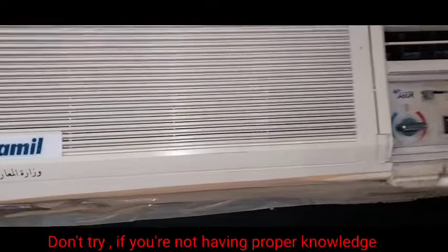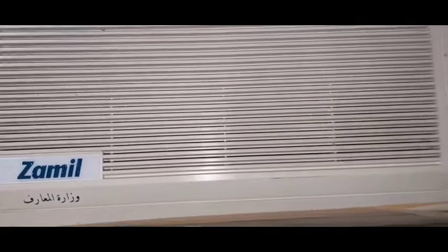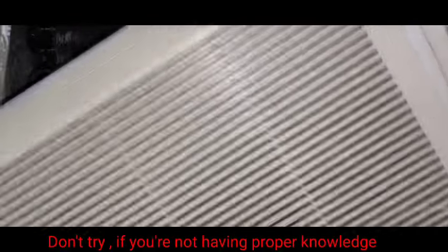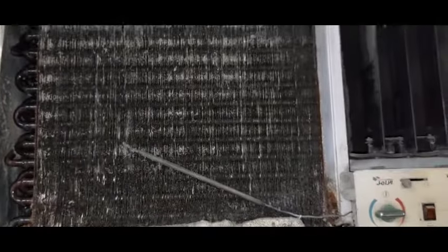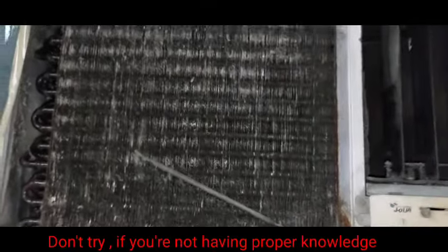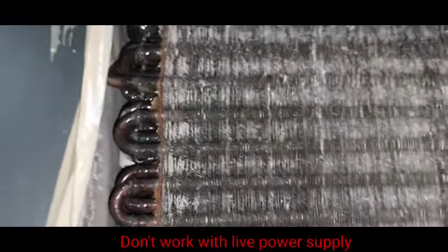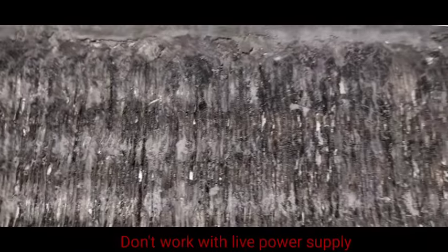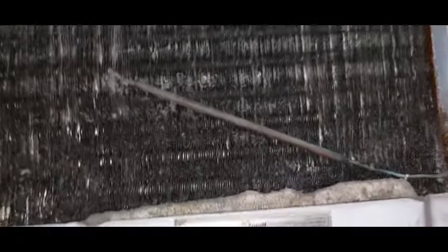Okay, so we will open the front grill cover now. Okay, so we removed the front grill. You can see there is water dripping because of excess cooling. There is no trip, and these fins are already clogged because it's very old, 2003. But now our problem is mainly the thermostat, so we'll concentrate on the thermostat.